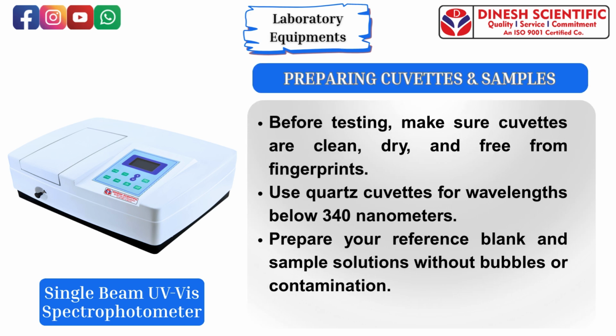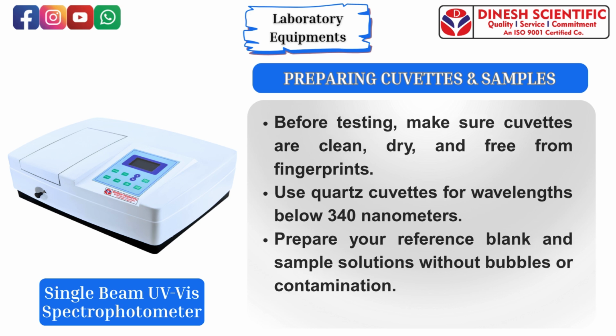Preparing cuvettes or samples. Before testing, make sure cuvettes are clean, dry, and free from fingerprints. Use quartz cuvettes for wavelengths below 340 nanometers. Prepare your reference blank and sample solutions without bubbles or contamination.